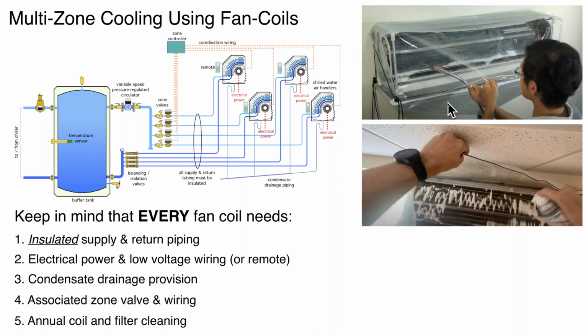You know, if you have a very large building, yeah, multi-zone cooling is probably reasonable. But in a typical 2,000, 2,500 square foot house, my experience has been typically in the summer, when the cooling system is on, you're cooling the whole building. You might have some airside dampers to do some zoning. And that, quite honestly, would be easier than dealing with all the infrastructure that you need for multi-zone cooling.